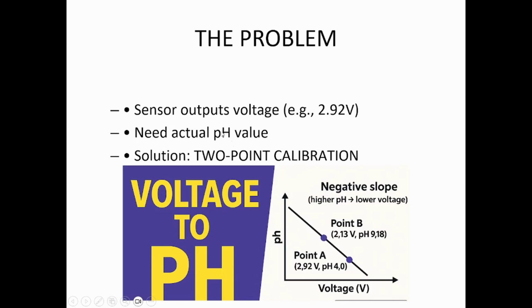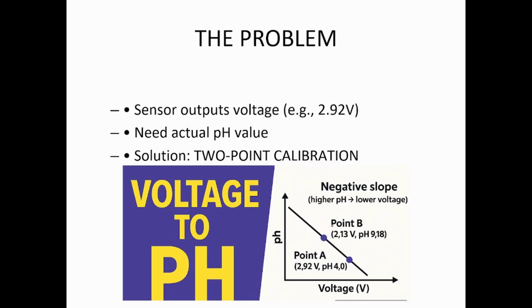So the problem is the sensor output is voltage. Now we need the actual pH value, and that's why we are doing this 2-point calibration. So basically we are doing voltage to pH conversion only, right? Now what this 2-point calibration is: let us say here is 1 point and here is 1 point, right? And now we have 2 points. So basically we can draw a line which is fitted through these 2 points.